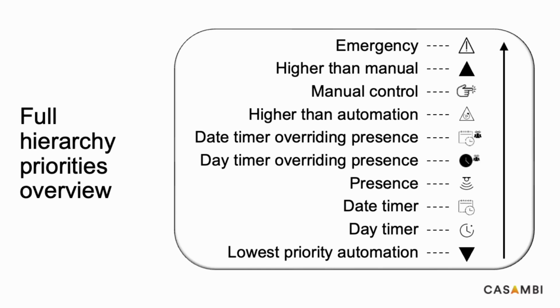This of course increases possible functions that you can achieve within the system, increases the flexibility of the system, but it also increases the complexity of programming and means that you've got to be more aware if you're using manual control with the control priority feature to activate a scene at a different priority level than manual control, because you then have to be aware that you might at some point in time have a switch that's triggering at higher than manual, and then you wonder why other switches can't control the luminaires because they're only controlling at manual control priority. So it takes a bit of careful planning to use the option.